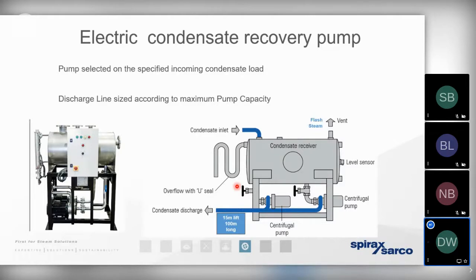One, we can only pump a liquid. We can't pump a biphase. And two, we can't pump a liquid if it's at a temperature any higher than 100 degrees. Because if that were to happen, that rapid phase change and that flash steam, as we saw, from the fall in pressure and temperature, would result in that pump cavitating and failing. And those pumps would be quite costly to replace. And until such a time that we could replace those pumps, that valuable hot condensate would back up and it would be discharged to waste across an overflow.